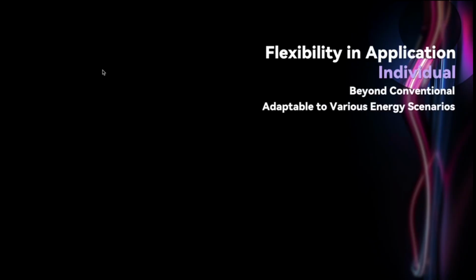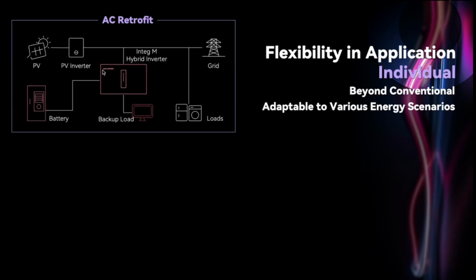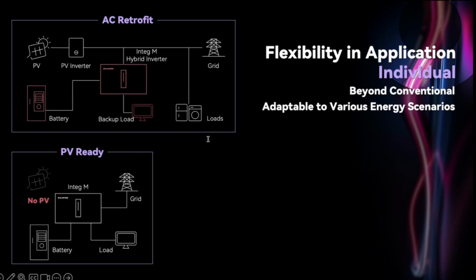Beyond that, the system also offers amazing flexibility for different energy scenarios. For example, if a customer already has an on-grid PV system and wants to add storage without changing the existing setup, our inverter is fully compatible, perfect for AC retrofit projects. The inverter inside this system can accept other brands' PV inverters, and we can also connect with our Solinteg on-grid inverter for better system management. Besides that, we are now designing a grid-forming inverter that can allow this AC retrofit system to run even when the grid is unavailable. And if the user doesn't have PV yet but plans to install it later, no problem.